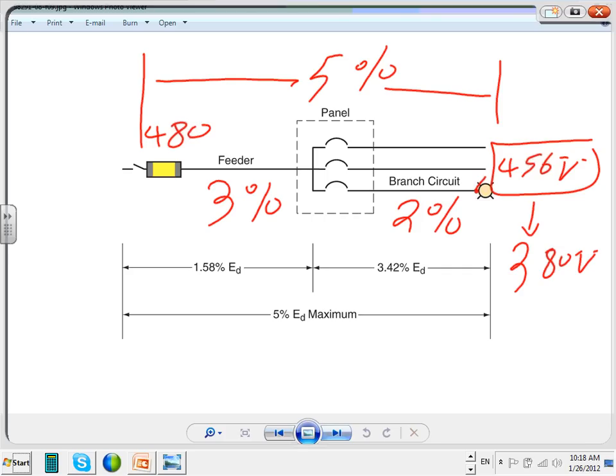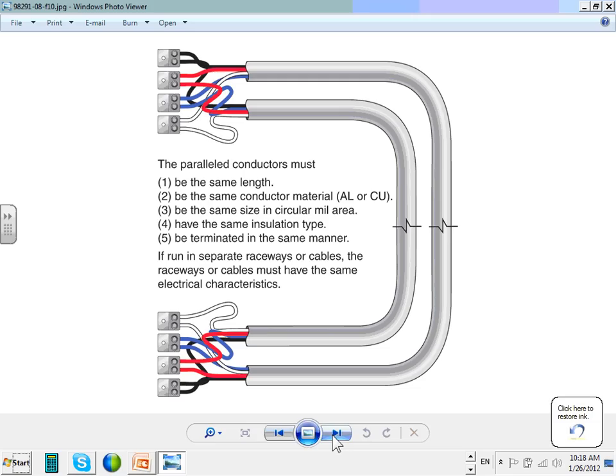Sucking more current, they're not rated for the current. What's going to happen to them if they suck more current than what they're rated for? Heat starts building up. Heat creates what? Fire. So that's a few things, guys, about the voltage drop. And we will do the voltage drop calculation, as I said. This is just a quick review.